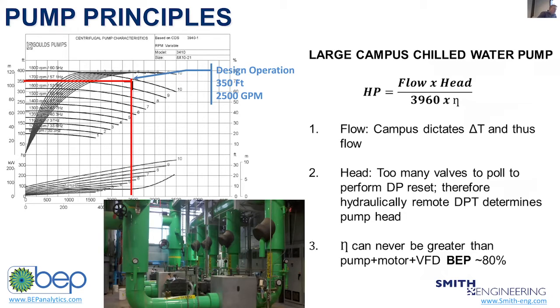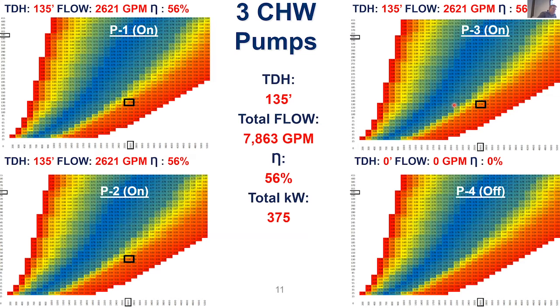They're running pump 1, pump 2, and pump 3, and pump 4 is off. They're sending out 7,863 GPM to campus at 135 feet of head. This is the operating point. They're on VFDs, so we're all happy. The VFDs are turned down, maybe at 70% speed. I don't have speed on here, but it's a little bit irrelevant for this example. We're all happy, but we don't have any idea what the pumping efficiency is because we don't have those analytics brought in. That's a simple formula. I just take that previous formula, solve for efficiency, and put that in my controller, right? But I'm running at 56% efficiency, which is not good. Total kW consumption is 375.